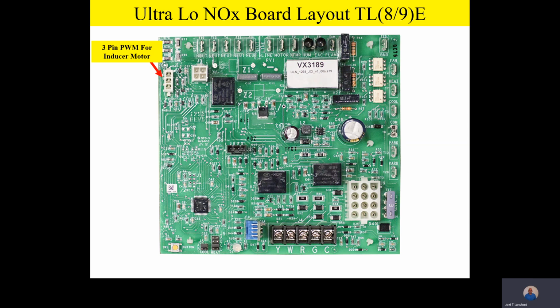As we come around the board, we see we've got a 3-pin PWM for the inducer motor. Now what this is, team, remember, it's a pulse width modulation. So here's how this works. The inducer motor is a high efficiency type of motor, and so it has power to it all the time. But hang on a second, it's just sitting there waiting for a command, a 24-volt command. Well, that's what this 3-pin PWM jumper is for. It'll actually put a pulse width modulation, which is just a DC voltage, to that inducer draft motor to tell it what to do. So again, this high efficiency induced draft motor will have power to it all the time, and then it's going to be commanded on what to do with this 3-pin pulse width signal, which is a DC voltage signal to command the motor.